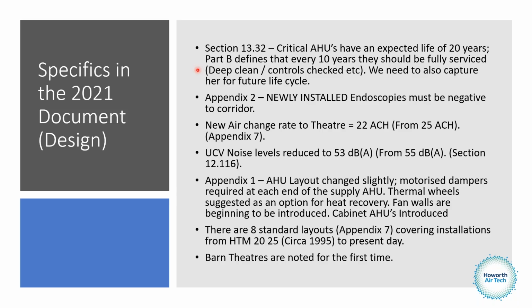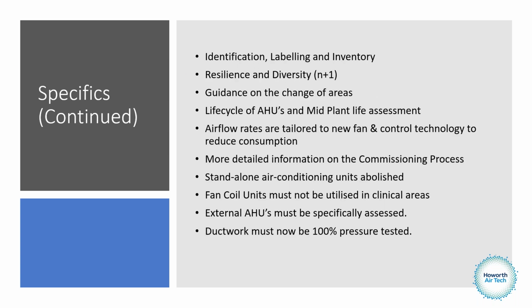There's 4 new air handling units that we can take advantage of, which I'm going to cover shortly. 8 new operating theatre layouts that goes from 2025 all the way to current day, and barn theatres are noted for the first time also. Lots of other things we need to consider. Identification, labelling and inventory. That label on the air handling unit has a minimum height of 100 millimeters now, which may seem excessive, but it's a question that needs to be answered.